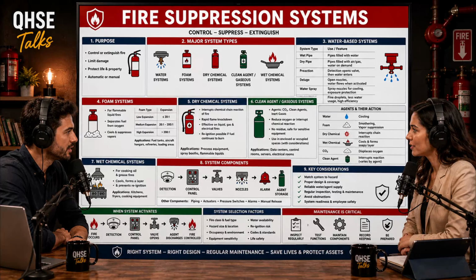But how does air pressure hold back massive water pressure? Water is much heavier. It relies on surface area differentials. The design of the clapper valve exposes a much larger surface area to the air side than the water side, usually about a 6-to-1 ratio. Oh, clever. Yeah, so a relatively low air pressure, like 40 psi, can successfully hold back a much higher water pressure of 100 psi. So what happens when a fire starts in the warehouse?